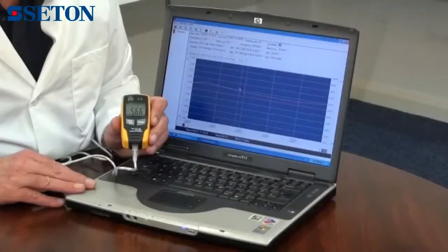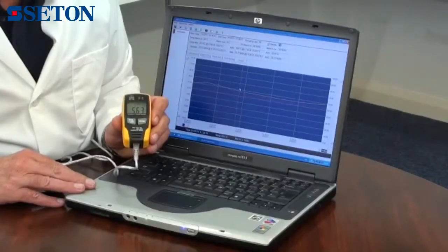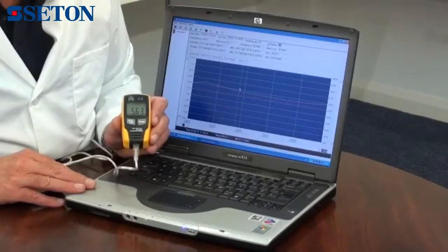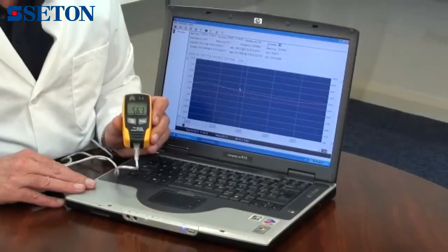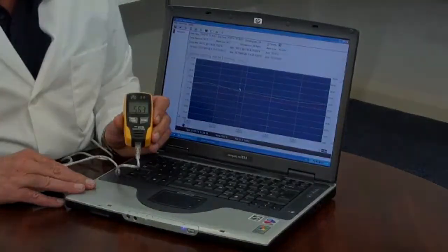The USB connection cable, with software loaded onto a PC or laptop, facilitates programming of parameters or the download of recorded data. The user-defined parameters are a delayed start time, setting of the logging rate from once every 10 seconds up to once every 24 hours, and a minimum-maximum alarm limit for temperature and humidity.